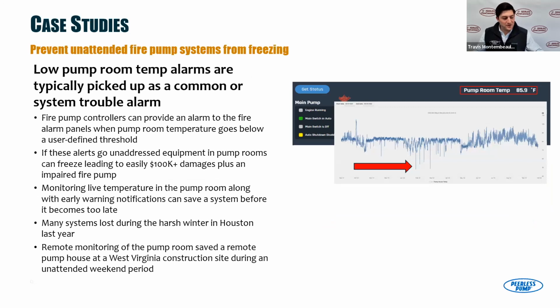Okay, a couple other cases here, and we'll go a little bit quicker because I do want to get to the demo. Monitoring pump room temperature, for example: sending an alert when pump room temp drops below a threshold that you specify. Fire pump controllers today have pump room temp monitoring, but it comes through as an alarm. And unless you have the extra contact specified and wired to your remote alarm panel, you don't know what that root cause is and what's driving it.